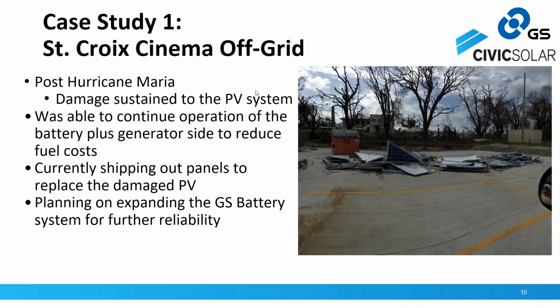But on the positive note, we were able to run the generators in combination with the battery bank to handle peak surges and lower the overall fuel consumption of the diesel gensets, causing further fuel savings on the site, even without the PV. So the diesel gensets stayed, they didn't have to run as long, and they were able to provide power to the site post-storm.